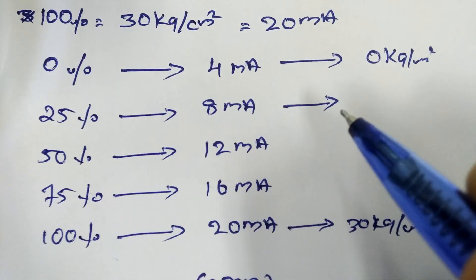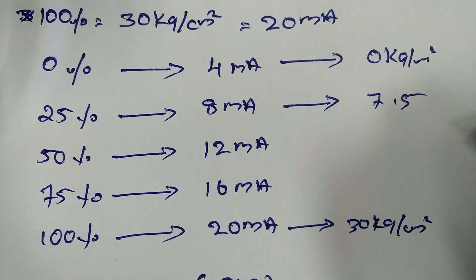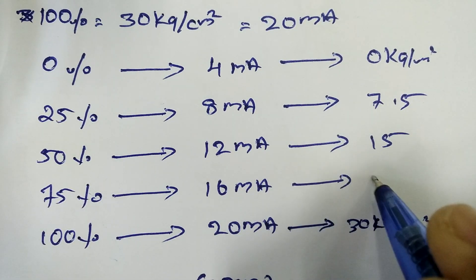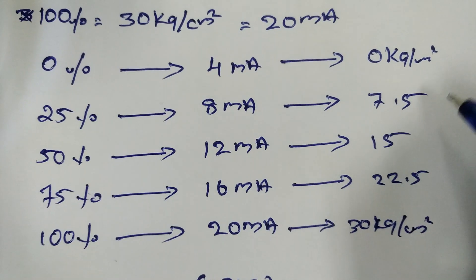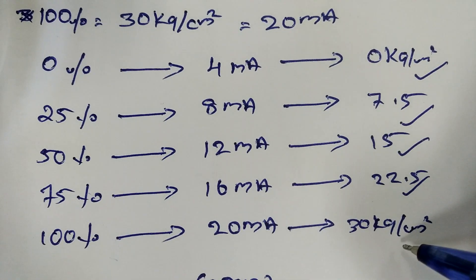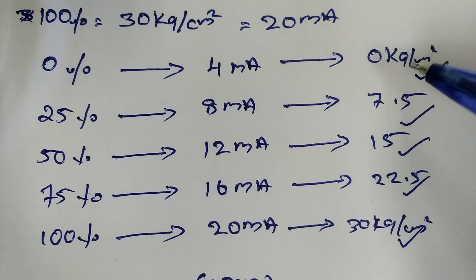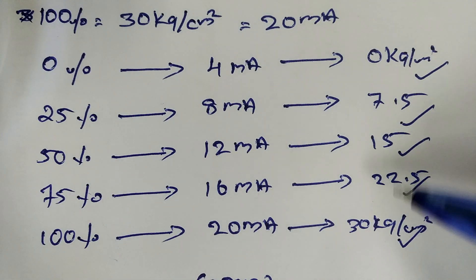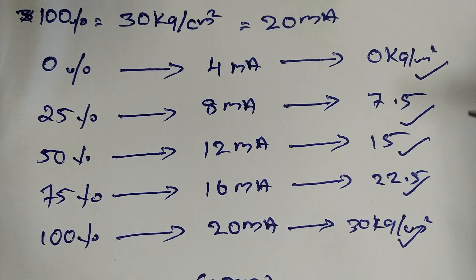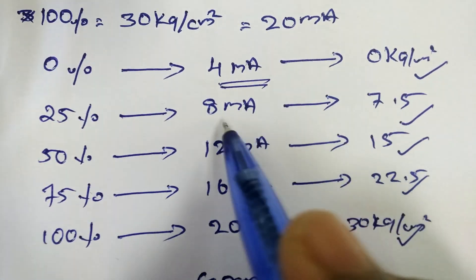Applying the calculated values: 7.5, 15, and 22.5 kg per cm². We use a comparator pump or hand pump, which is available to us, and we calibrate the transmitter using these values.